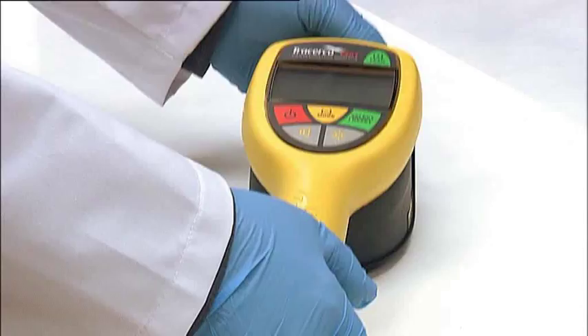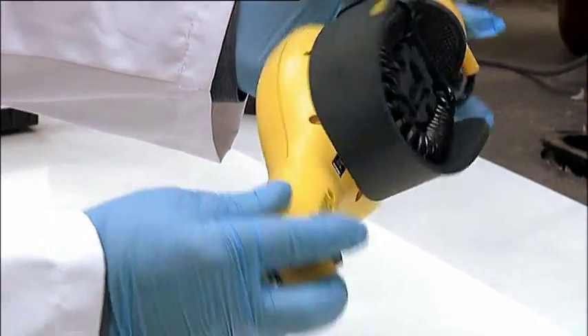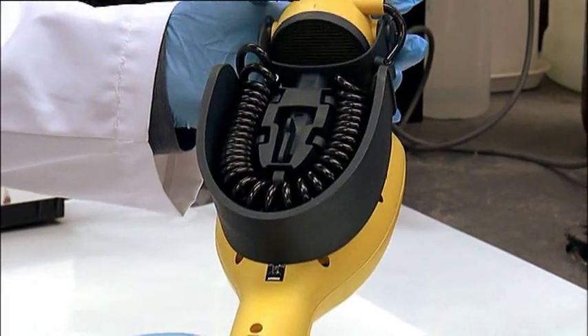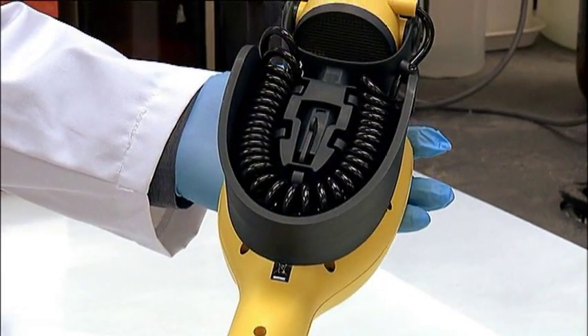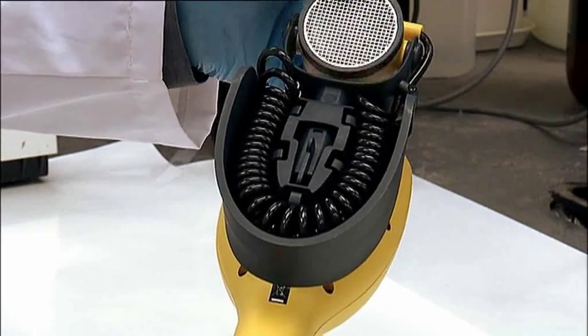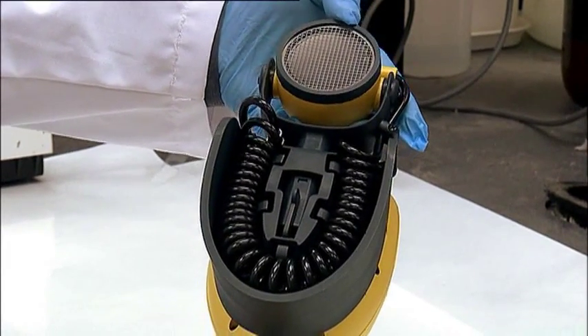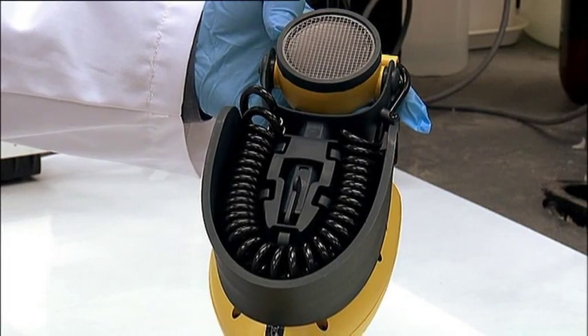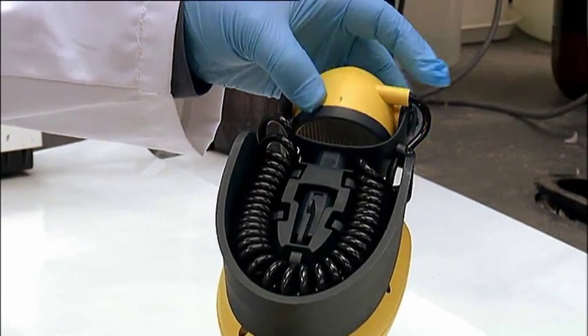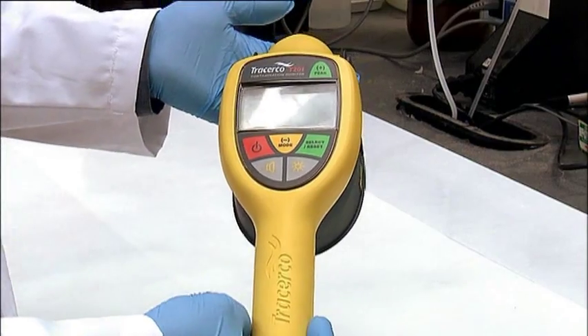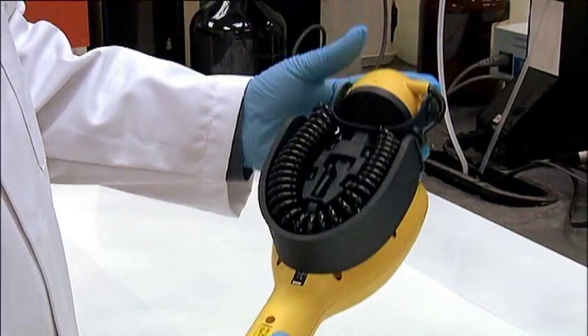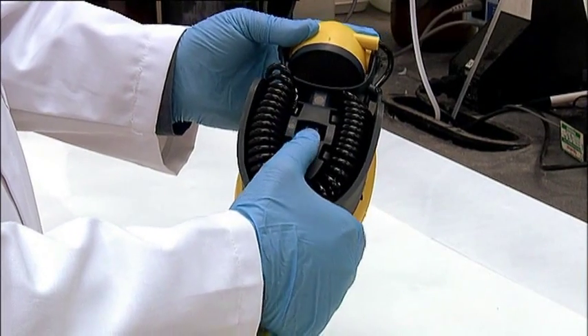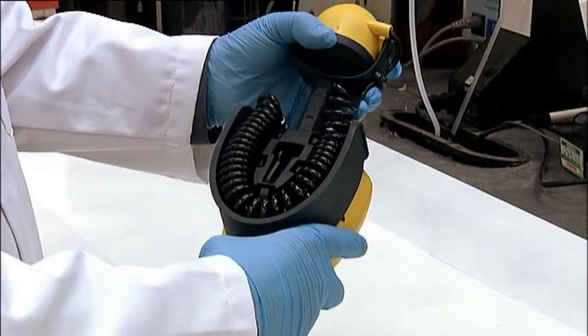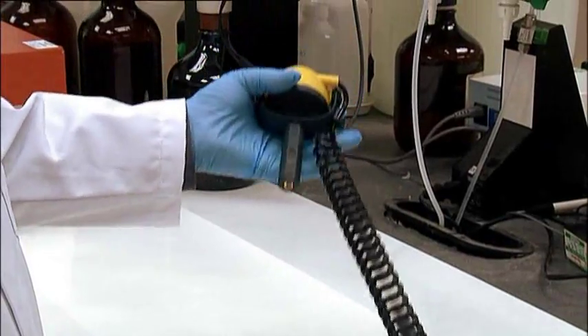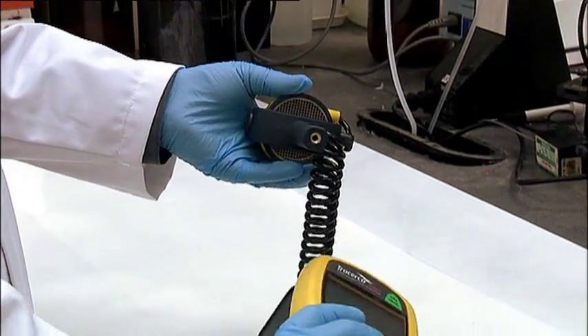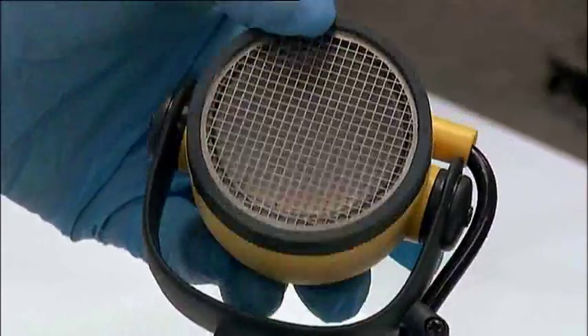The T201 is the unique Tracerco Intrinsically Safe Radiation Contamination Monitor. The body is constructed of a special easy-clean nylon polymer, and the radiation detector is of a thin window Geiger counter type, housed within the lower skid arrangement for both convenience and to protect the detector head. The detector can be detached from the body of the instrument for remote monitoring operations. The flexible cable allows for operation up to 1 metre from the main instrument. The face of the thin window detector is protected by a wire mesh screen.